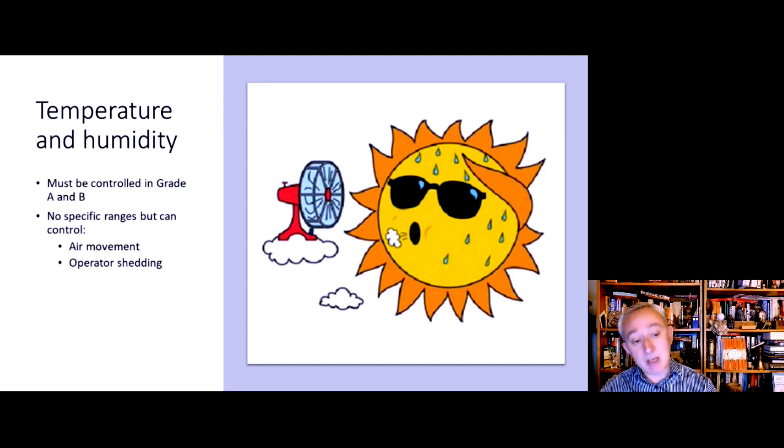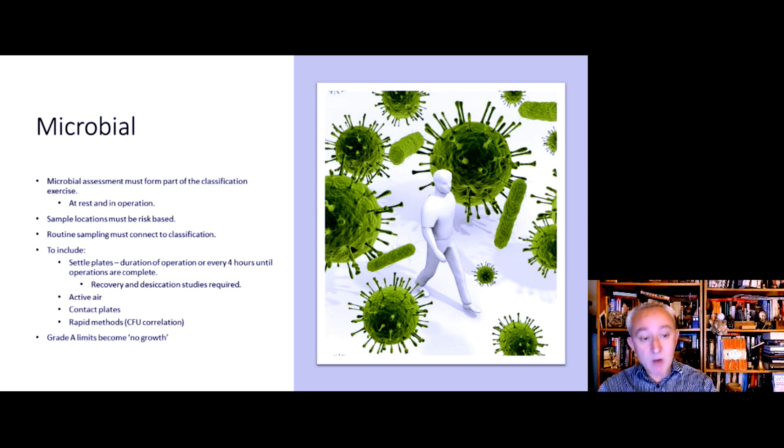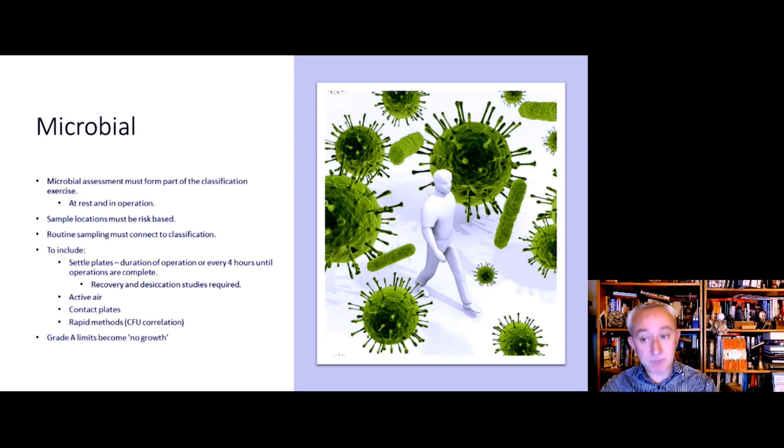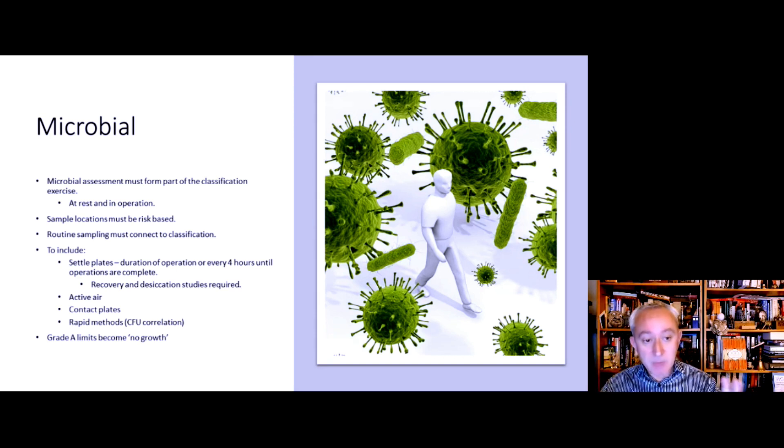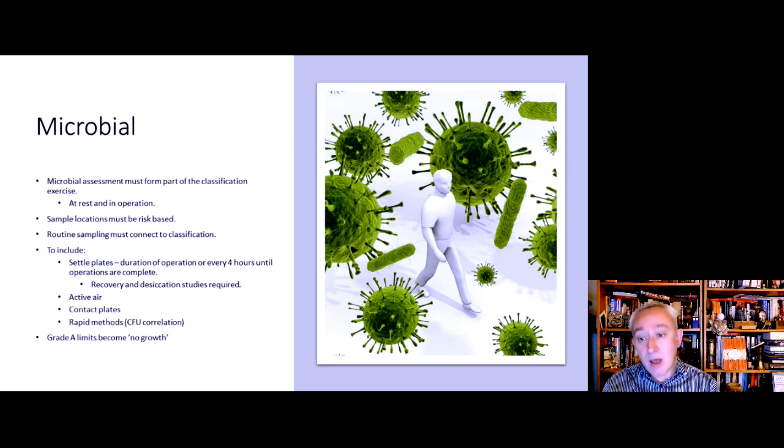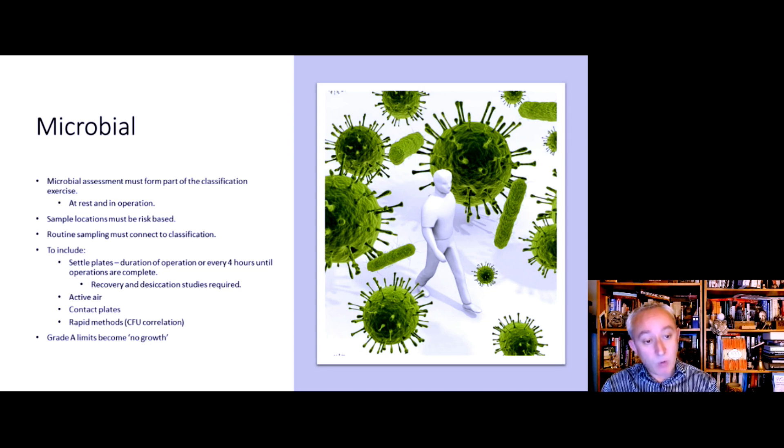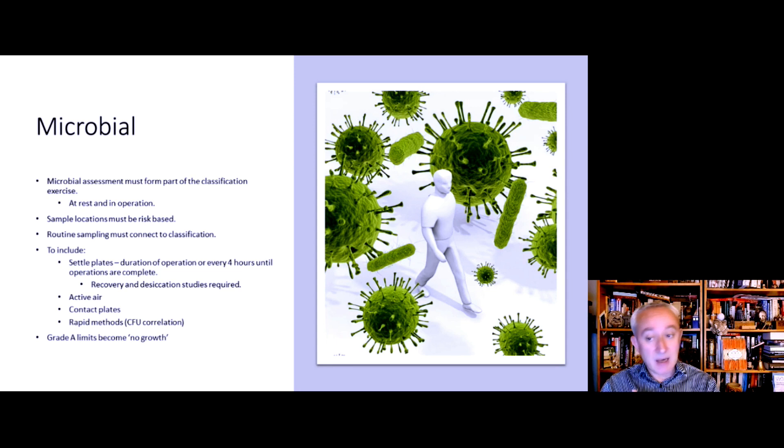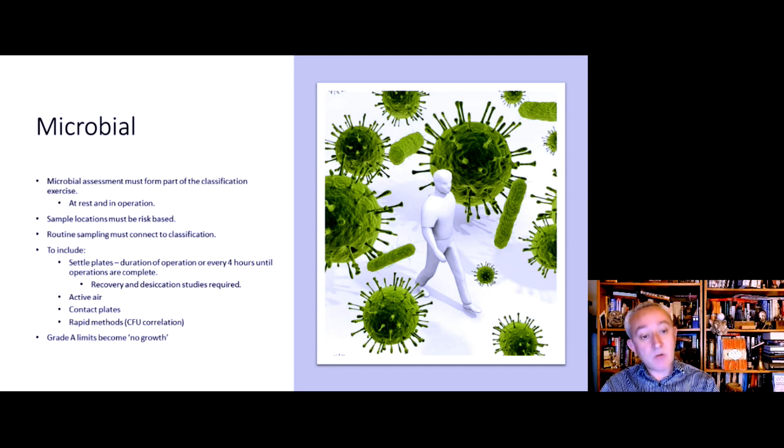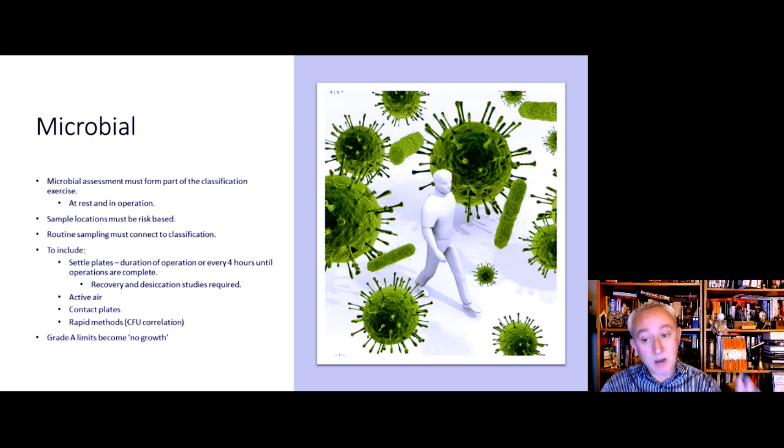There also needs to be a microbial assessment as part of the classification exercise, and that needs to be conducted at-rest and in-operation. The sample locations need to be determined by a risk assessment such as HACCP (hazard analysis critical control points), and it should include settle plates. The settle plates are exposed for the duration of the operation or the plates changed every four hours, whichever is necessary. For grades A, B, C, and D, there need to be active air samplers and contact plates. If we're going to use rapid microbiological methods, then we should have an understanding of whatever the unit of measurement is for the rapid method can correlate with the classic colony forming unit, so we have an idea of microbial recovery and contamination levels.